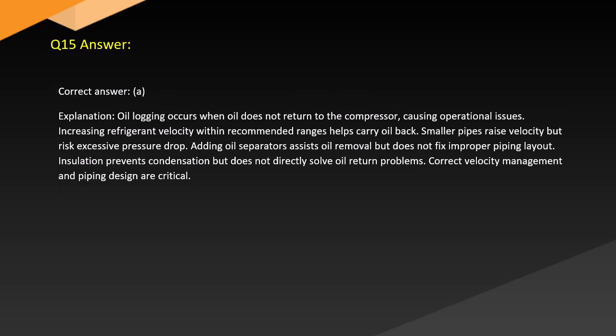Answer. Correct answer: A. Explanation. Oil logging occurs when oil does not return to the compressor, causing operational issues. Increasing refrigerant velocity within recommended ranges helps carry oil back. Smaller pipes raise velocity but risk excessive pressure drop. Adding oil separators assists oil removal but does not fix improper piping layout. Insulation prevents condensation but does not directly solve oil return problems. Correct velocity management and piping design are critical.